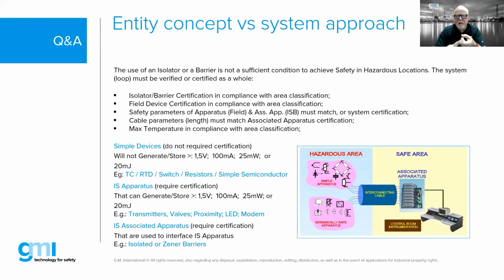So there are some things to keep in mind: simple devices and intrinsically safe apparatus. Simple devices do not require certification. Things like thermocouples, RTDs, switches, resistors are all examples of simple devices. They don't generate or store those parameters. So a thermocouple used for a zone area does not require certification; we can use a standard off-the-shelf industrial or commercial thermocouple, RTD, or switch.